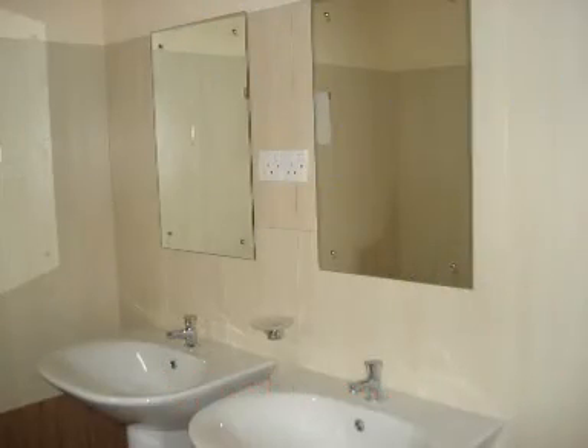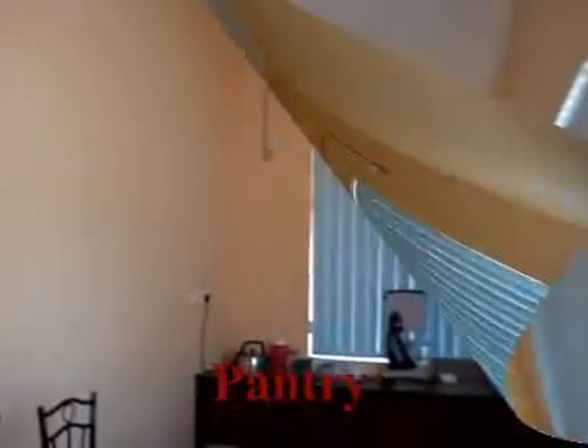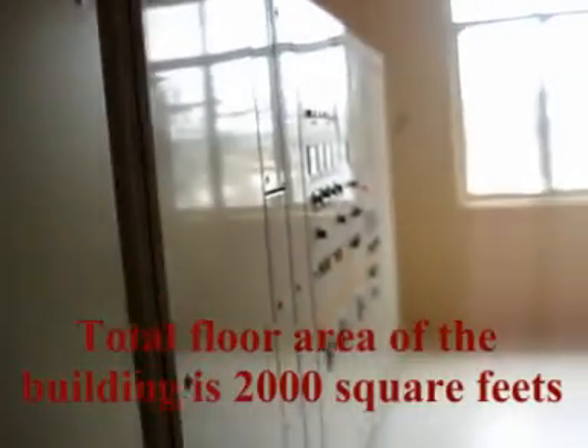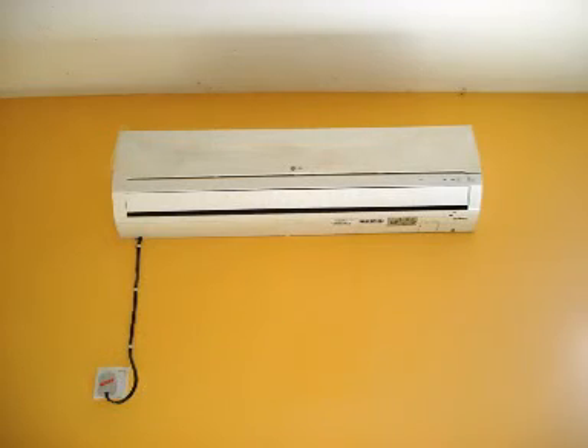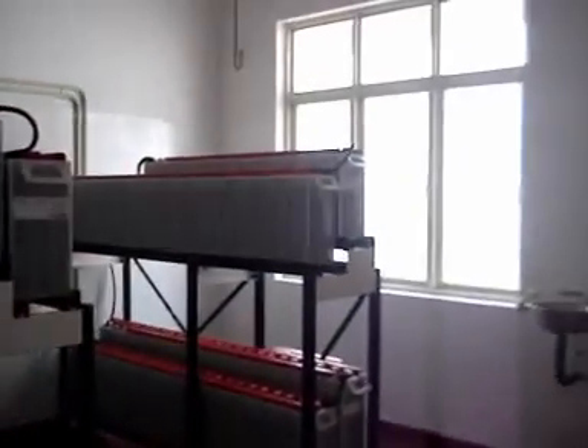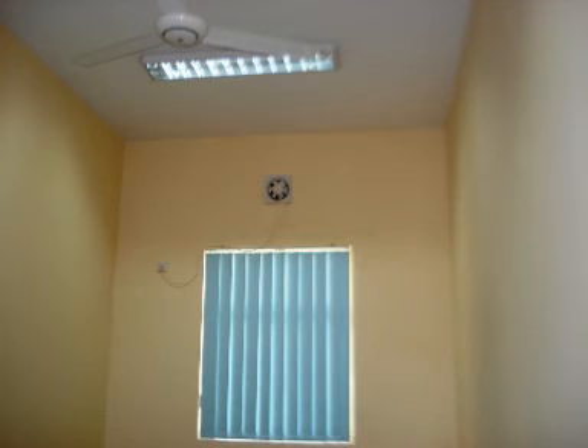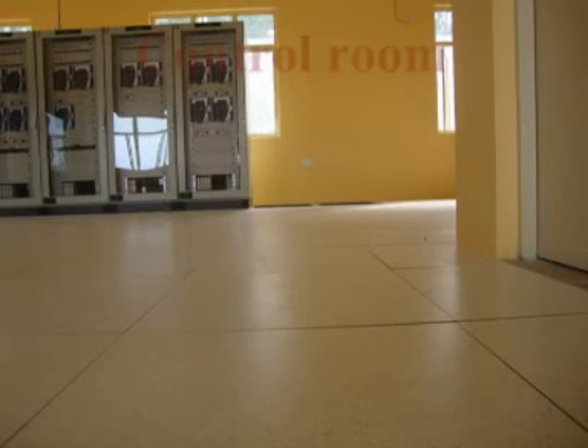A single-story control building is constructed with all control facilities and other facilities for operators who are on duty. The total floor area of the building is 2,000 square feet. The entire building is fully air-conditioned except the battery room, storeroom and restroom. However, the restroom is ventilated through fans. Exhaust fans are provided for the battery room, storeroom and toilets. The building floor is tiled except the battery room and storeroom.